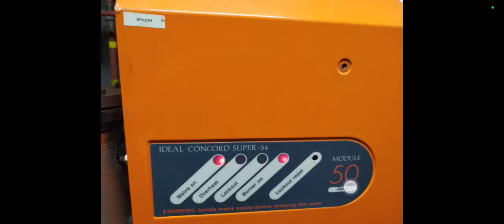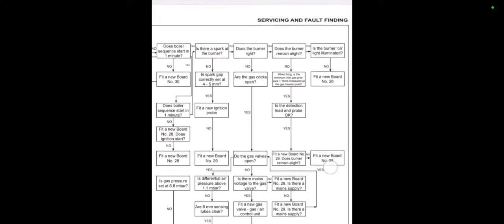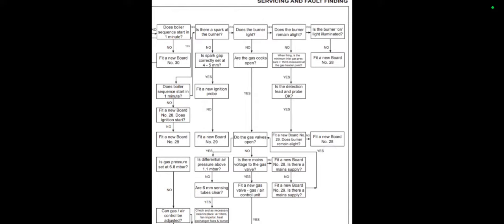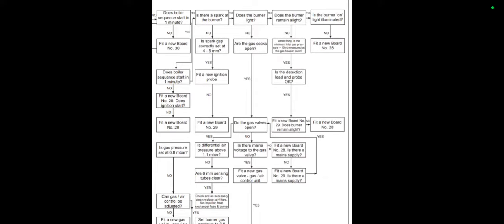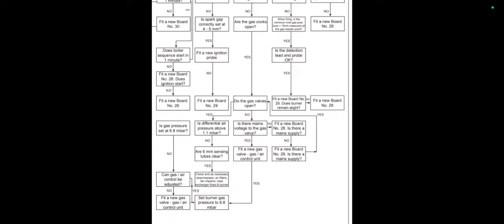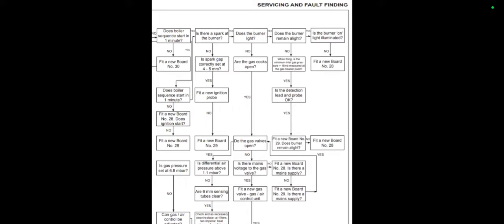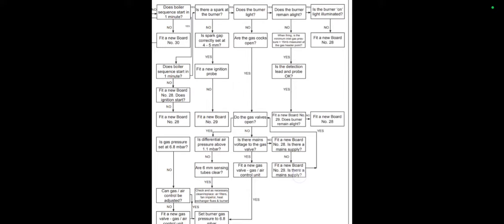This is the 50 kilowatt module of these. This is quite interesting information in the diagnostics. The fault finding is very good. It talks about the different boards that need fitting. And look here, is differential air pressure above 1.1 millibar? It says no. And then are 6mm sensing tubes clear? Yes. And so on. So it's very good, very helpful. It speaks of board 28, board 29, board 30.